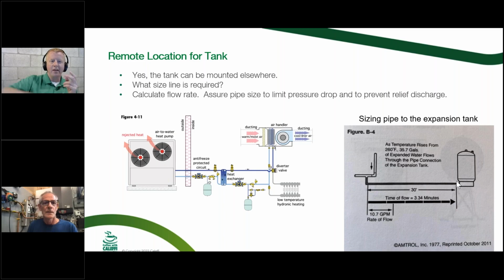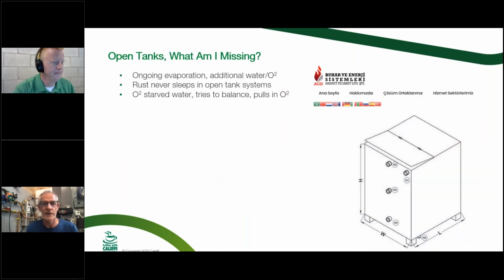Like you said, Bob, even if that 30 feet of pipe goes up and over, you're going to have trapped air in there. But if you've got an air elimination device that's properly functioning, that air is going to sooner or later get absorbed back into the water that's flowing throughout the system, and it'll get out of there. But yeah, a good purge valve might not hurt either. Essentially what happens in a compression tank is that air gets absorbed back into the water, and then if it gets vented out, you lose it. So that's probably what's going to happen to that air. It'll go back as the water cools, maybe in the summer, and then get vented out.